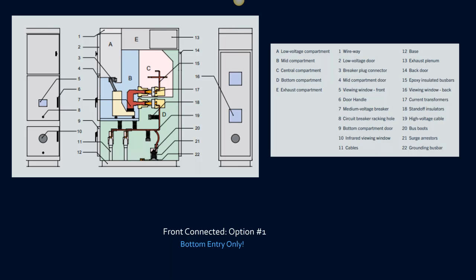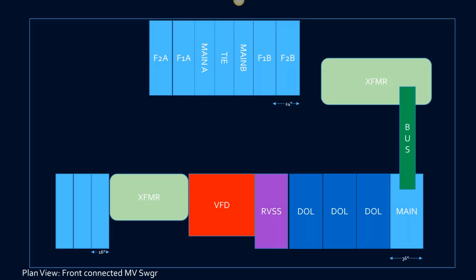It's a great design. This one happens to be arc resistant. There are some limitations, and one of those limitations is that this is bottom entry only. So you have to be willing to run all of the conduits underneath the building and through the concrete and that kind of thing. And there are several manufacturers who make this particular design. And so let's see what that does to our room. That reduces the footprint of the medium voltage switchgear greatly, even in a one high design.